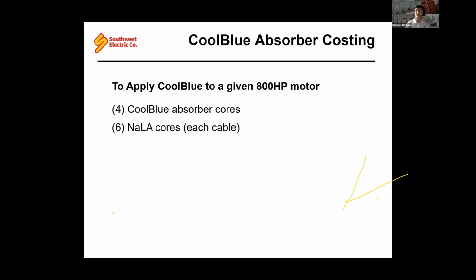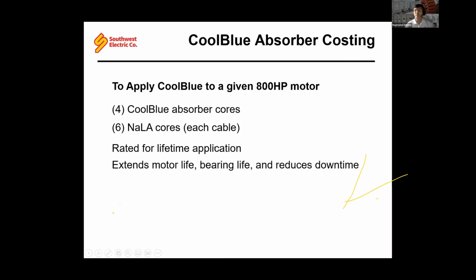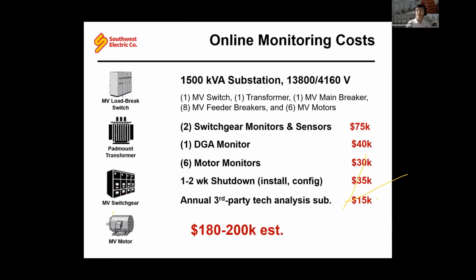So for that given 800 horsepower motor in our example, based on that size, you would need 4 of these CoolBlue absorbers, and then these NALA cores that go around each cable. They're, again, for the lifetime of the application, so a one-time investment, and a very, very manageable cost. So if we go back to our original example, and again, all this is about money. I'm trying to help budgets who want the online benefit but just don't have the significant investment needed to pull it off.